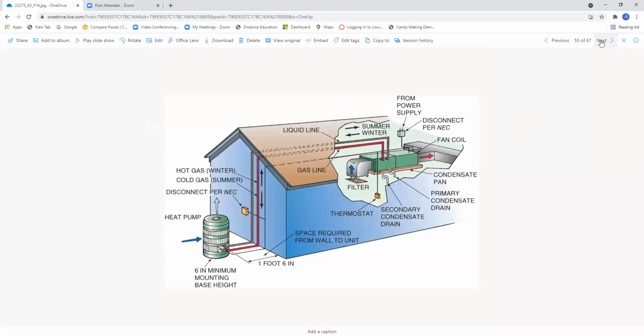Okay, we talked about this this morning in the PowerPoint presentation. Of course, this is your outdoor unit. This is your horizontal indoor unit. You've got your return air, you've got your supply air, condensate pan. This looks like a normal installation of a split system gas heat and air conditioning system, except in this case, you don't see a flue pipe, number 1. That's gone. You don't have a gas connection, number 2. In this case, we are reversing the flow of refrigerant in order to supply heat to the house inside.